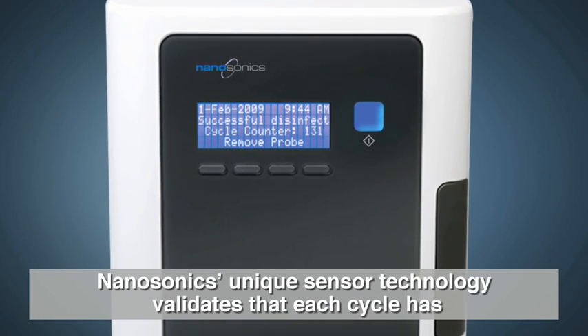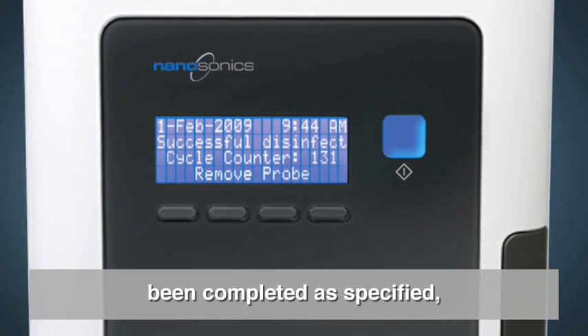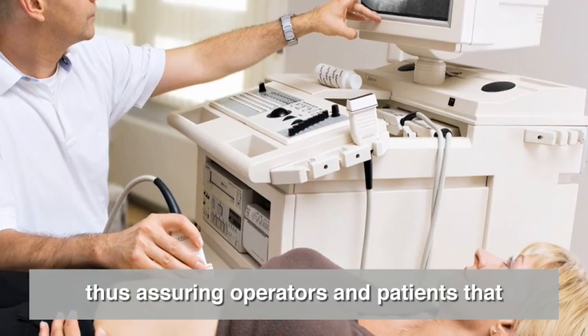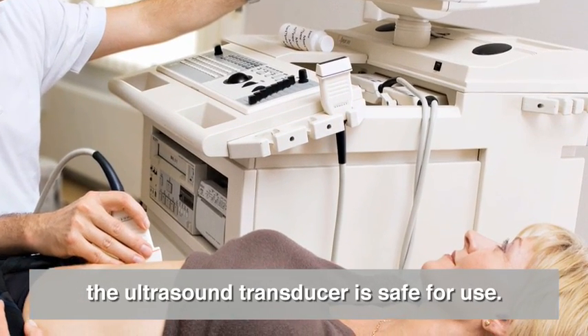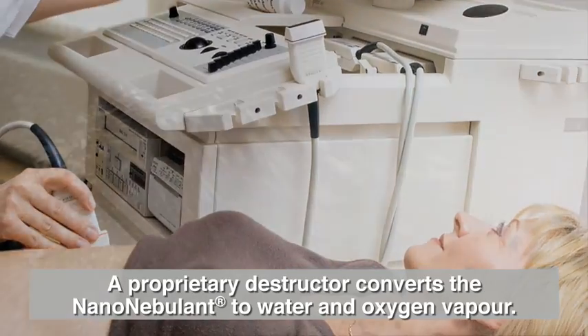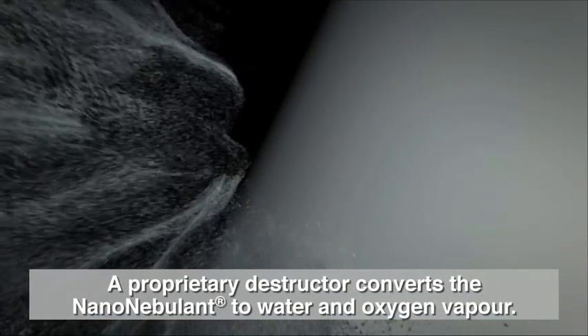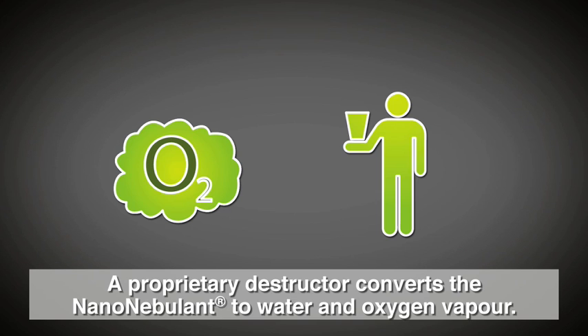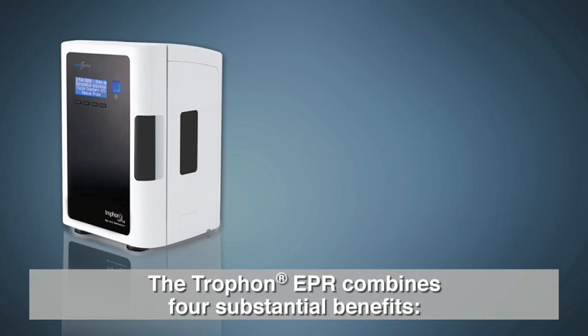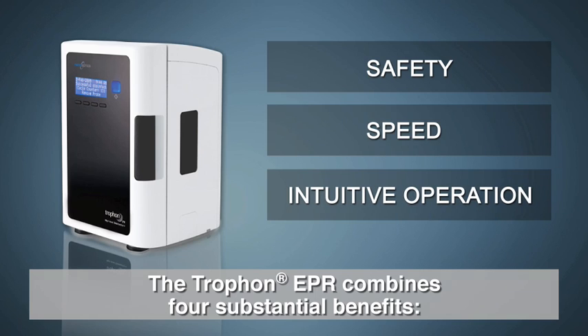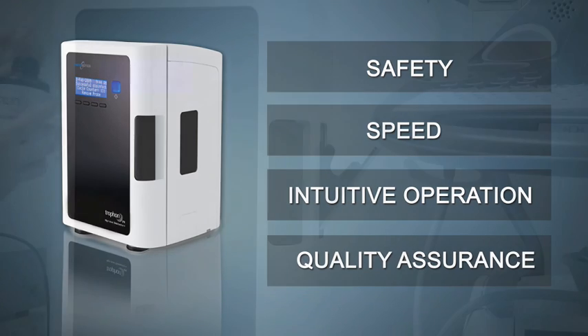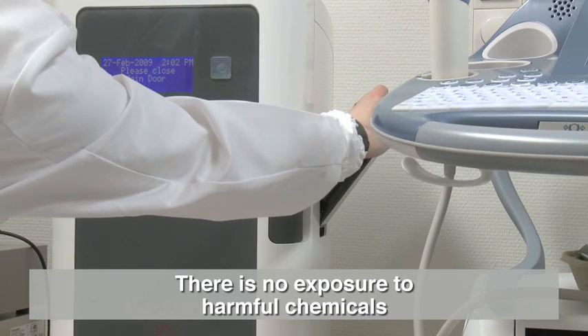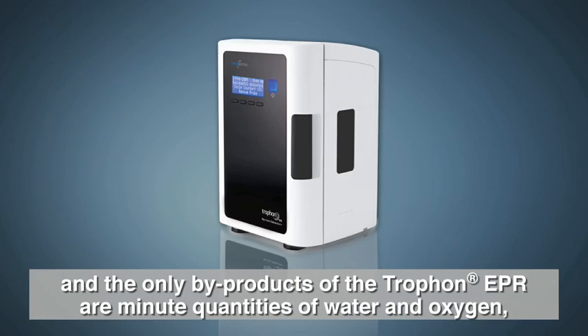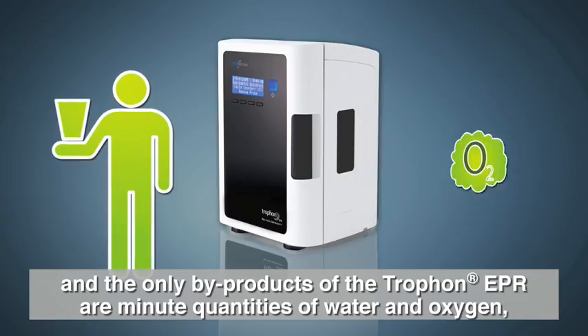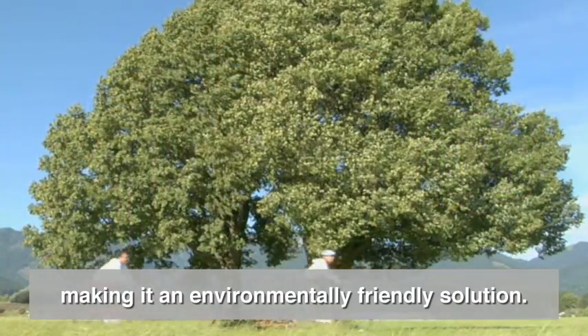Nanosonics' unique sensor technology validates that each cycle has been completed as specified, thus assuring operators and patients that the ultrasound transducer is safe for use. A proprietary destructor converts the nanonebulant to water and oxygen vapor. The Trophon EPR combines 4 substantial benefits: safety, speed, intuitive operation, and quality assurance. There is no exposure to harmful chemicals, and the only byproduct of the Trophon EPR are minute quantities of water and oxygen, making it an environmentally friendly solution.